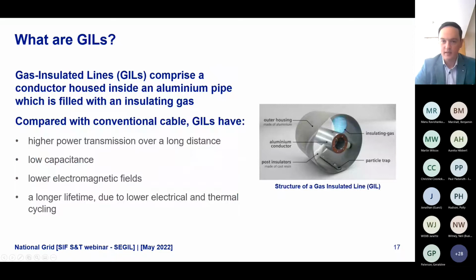So what is GIL? GIL is basically a pipeline with the conductor in the middle, surrounded by insulation gas. Compared with conventional cables, it has much higher capacity, especially over longer distances. As I said, with 3 pipelines, one per phase, it can deliver 3, 4, up to 6 gigawatts of power at high voltages. It has lower capacitance than cable, so there's less problem with grid stability and reactive power compensation. It has low electromagnetic field because it's shielded by the pipeline, and especially could have a longer lifetime due to lower electrical and thermal cycling, meaning it can run for decades, similar to gas transmission infrastructure.